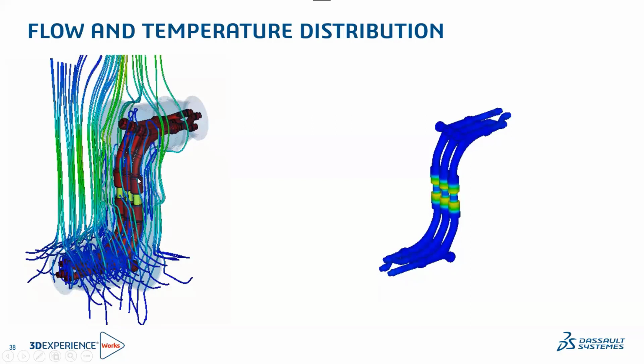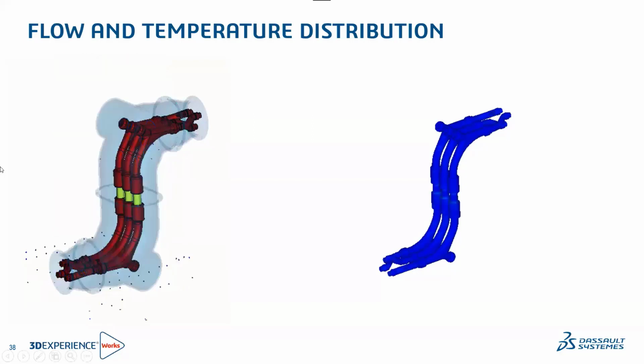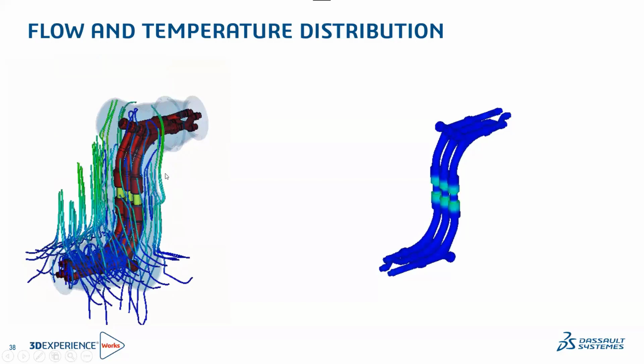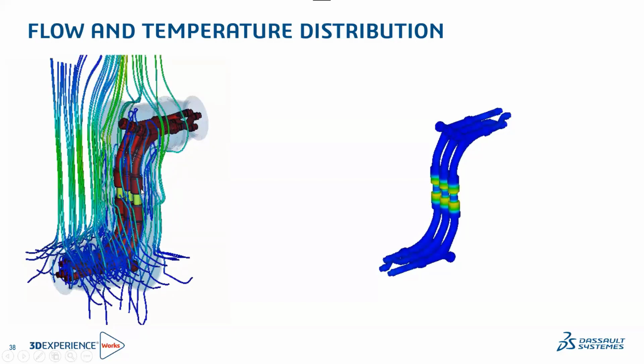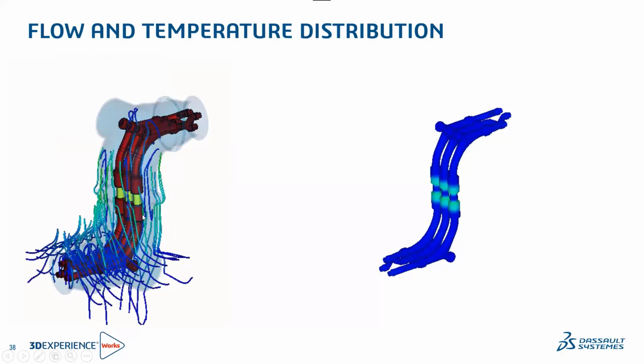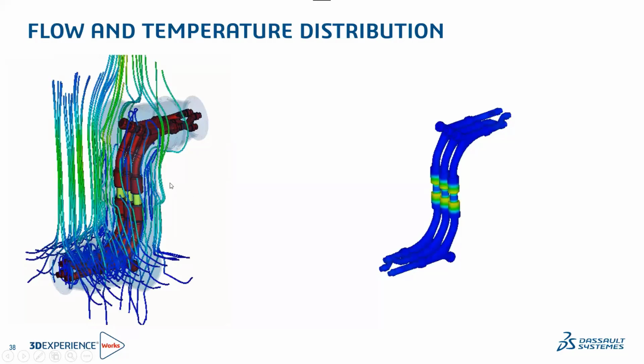You have SF6 gas, and I will let you know why we put SF6 inside those devices and not normal air. But just to stay on the thermal behavior, you can see that the velocity of the air around is faster than the SF6. This is normal because the viscosity of SF6 is higher than the viscosity of air, and this is why the gas inside has a lower speed than outside.